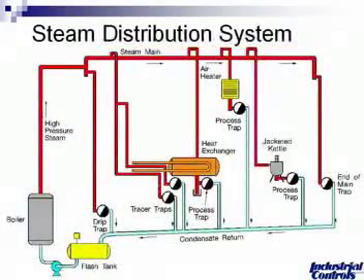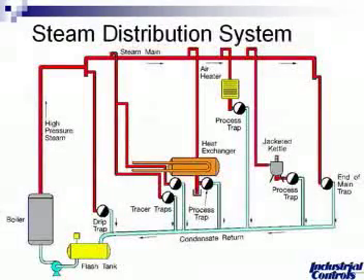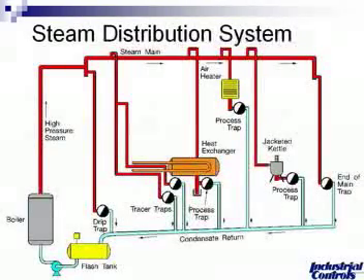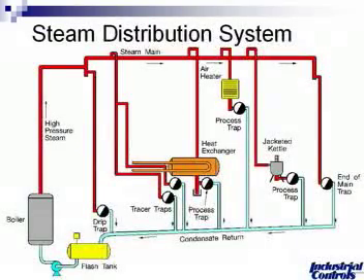This slide shows the basics of where a steam trap would be applied and how you would use it. You obviously have your boiler off on the left-hand side that will be distributing steam at a higher pressure. The reason you distribute the steam at a higher pressure is it's a very small specific volume, thus you can use smaller pipelines. You'll notice we have a steam trap at the end of main, generally at the low points in the main header. The steam would then be distributed to different process areas — for example, a low pressure air heater, a process heat exchanger, tracers, and jacketed kettles — and returned back to your flash tank for reuse to make steam again.